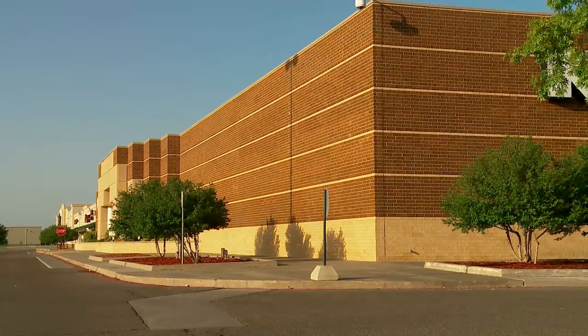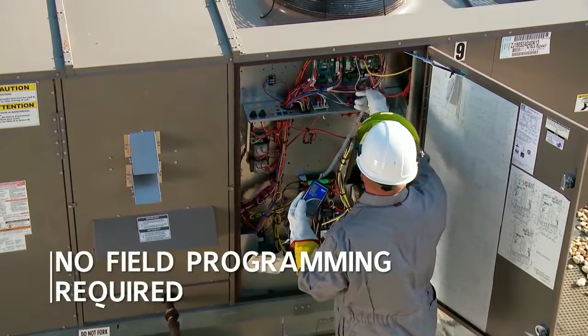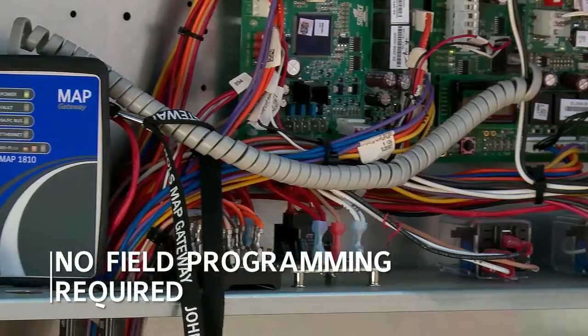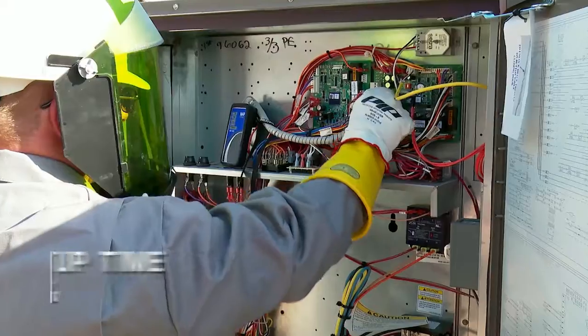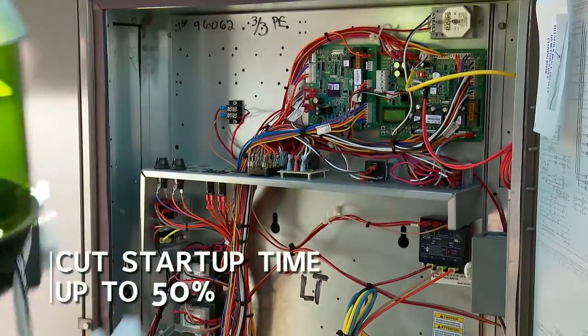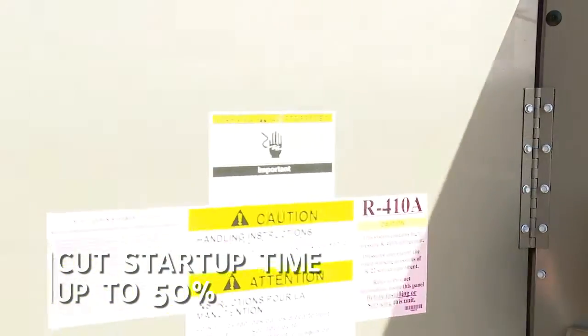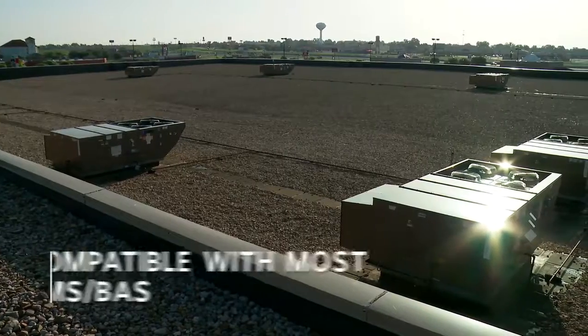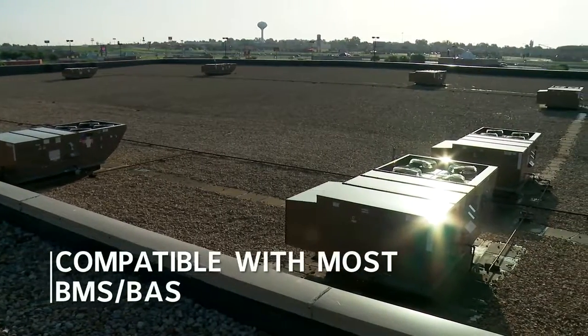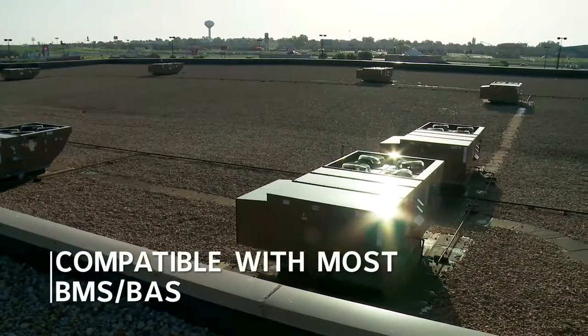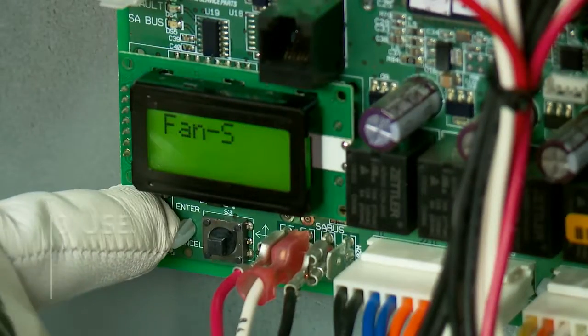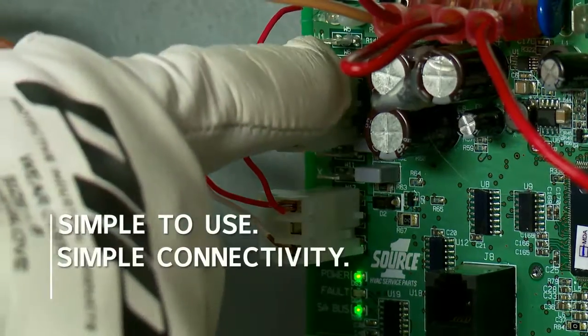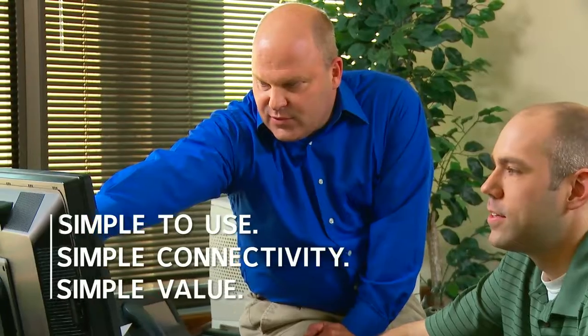For contractors, the Simplicity SE approach saves time because the controls are factory installed and commissioned. No field programming is required. In fact, an auto-commissioning self-test at startup cuts startup time by as much as 50%, and it easily connects with a wide variety of building automation tools to make facility managers and building owners happy. Simple to use, simple connectivity, and simple value.